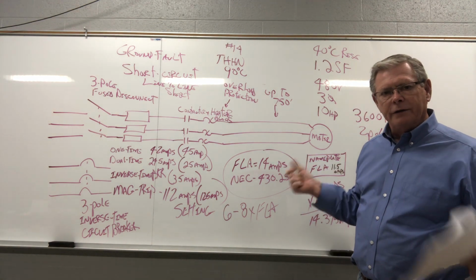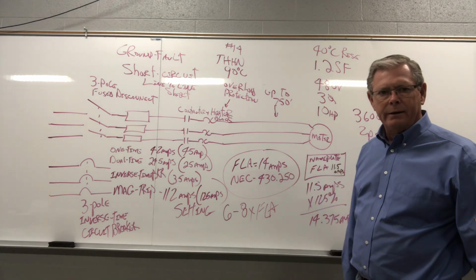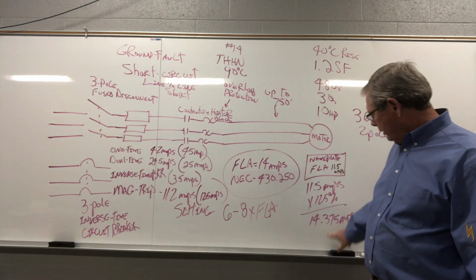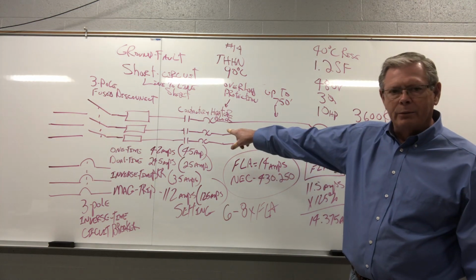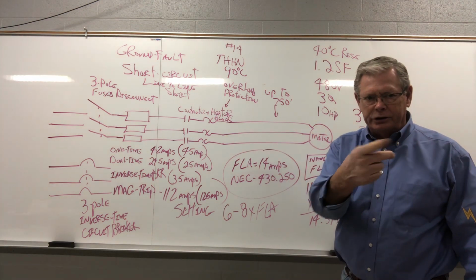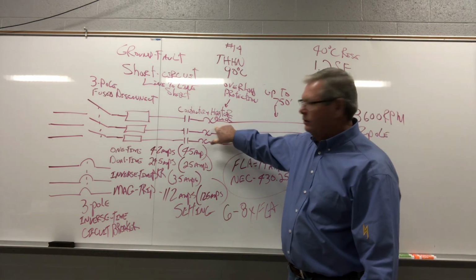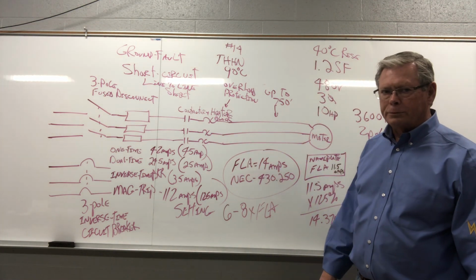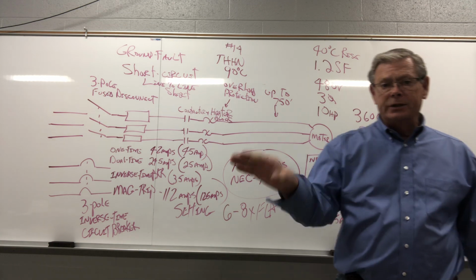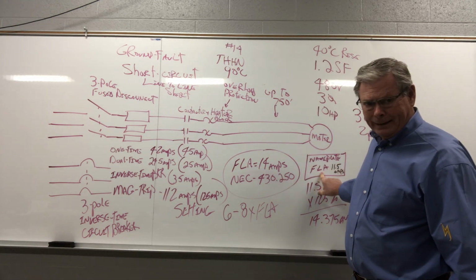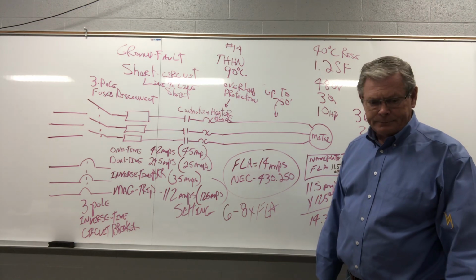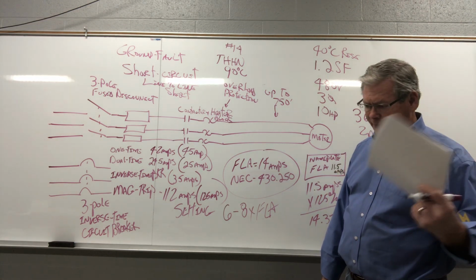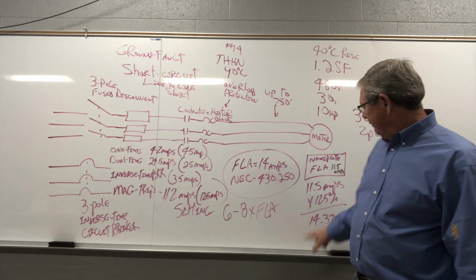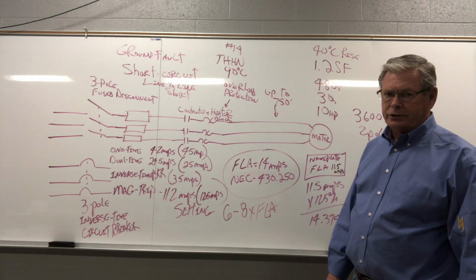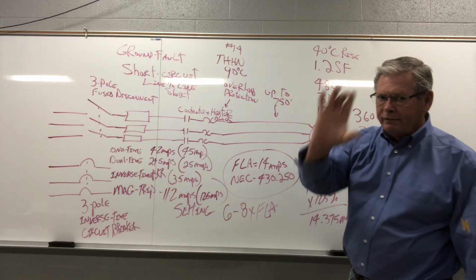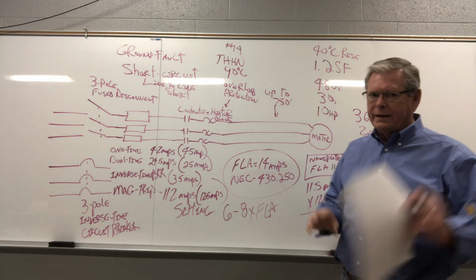But now you're using the full 10 horsepower of motor, because all this knows is it's going to trip out when those heaters get too hot. So it's up to us, you, me, to size these heaters right so that we can get full horsepower off the end of that shaft. Most of the time, if you just go straight by nameplate, most equipment's fine with that. But I've checked with motor shops and they verified this. They said most motors, whenever you use nameplate, most motors, you're asking for 80% of the horsepower. So we've got 20% left according to the NEC.